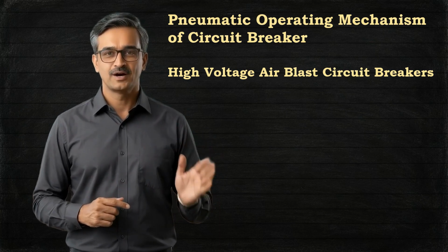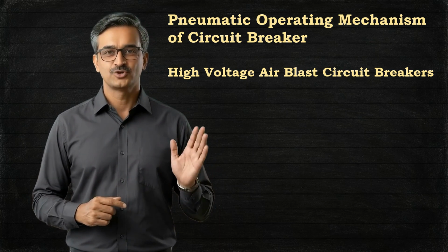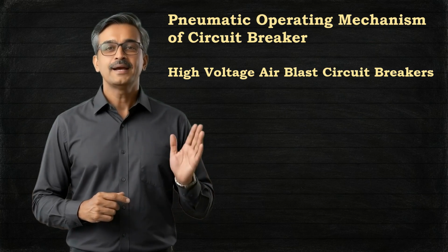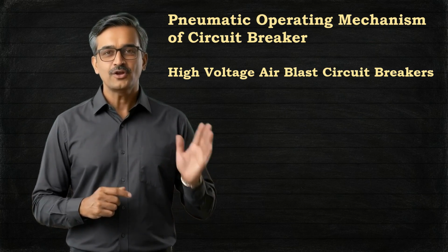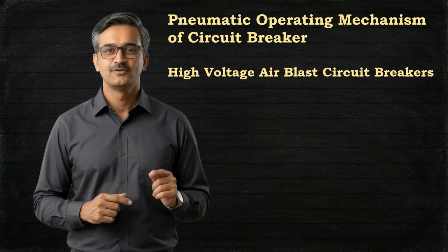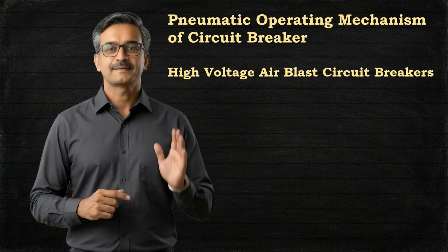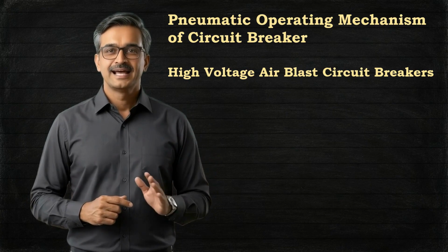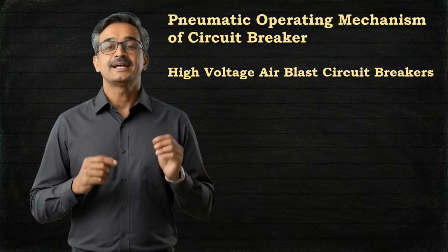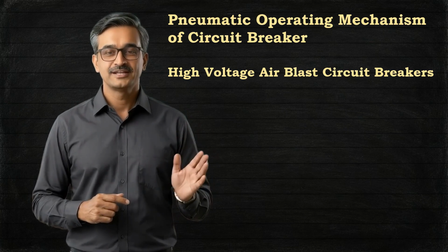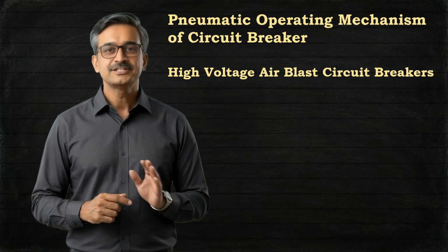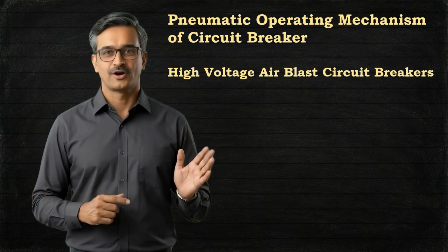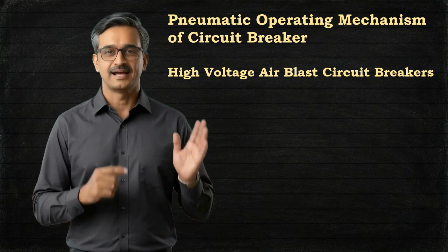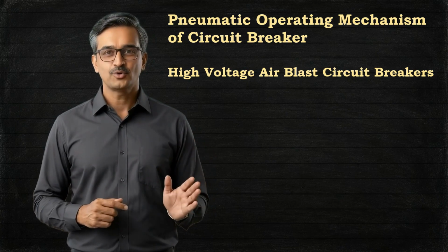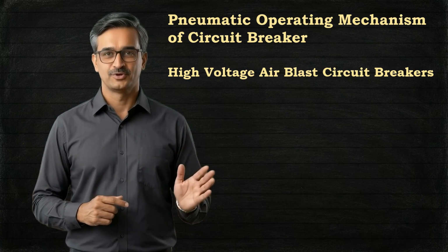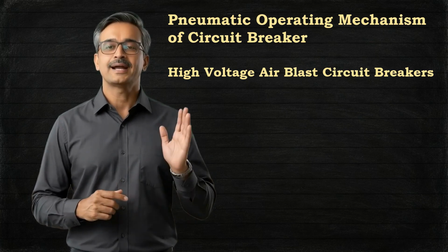Actually, when the closing command is passed through the solenoid actuated air valve, that means when a closing command is given to the solenoid closing coil, it lifts the valve and opens its passage. As a result, the compressed air stored in the air reservoir is suddenly released and expands, pushing the piston backward. This piston is mechanically linked with the moving contact of the circuit breaker. Therefore, as the piston moves, it pushes the moving contact to its closed position, thereby closing the circuit breaker.